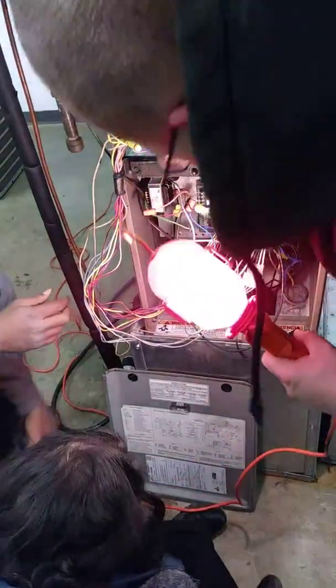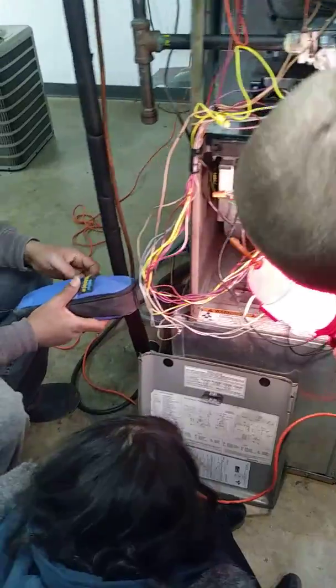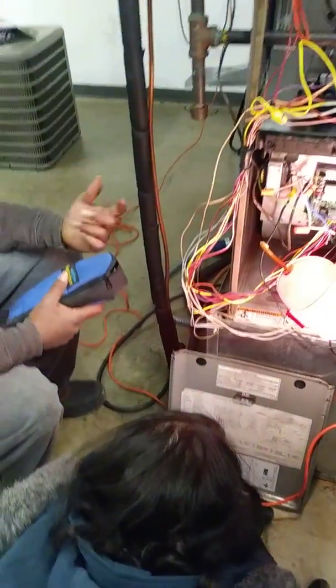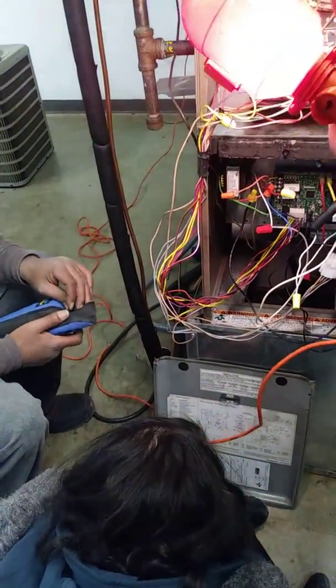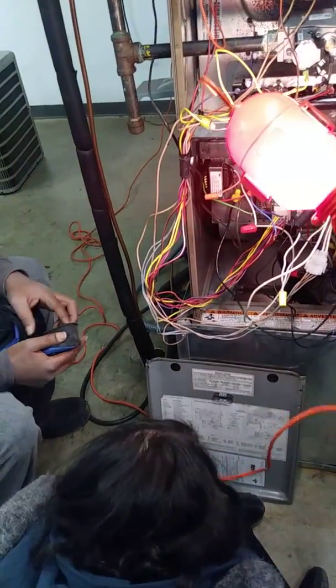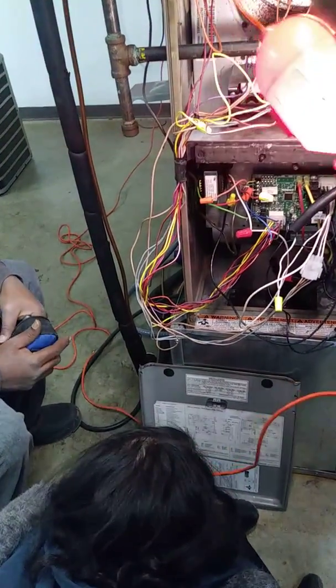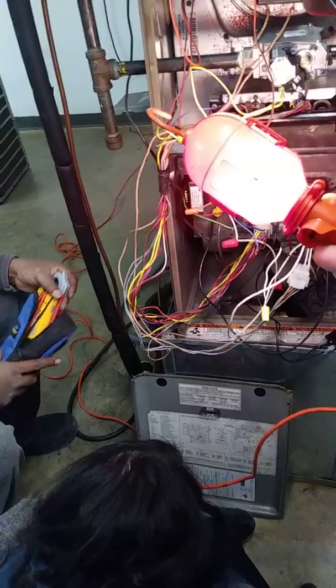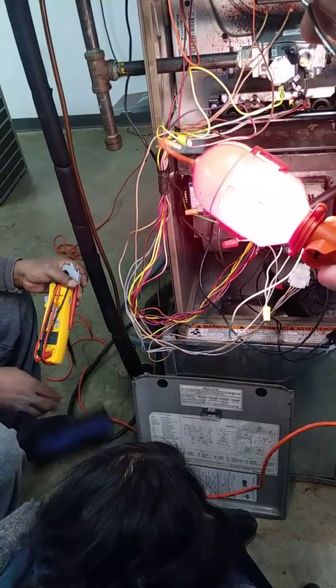It's just like with a contactor outside, it could be wired straight in to where you could pull the disconnect and it still run, because people still air condition. If you don't know anything about electricity, you might not mess with it if you pull that breaker out and it's still going outside.